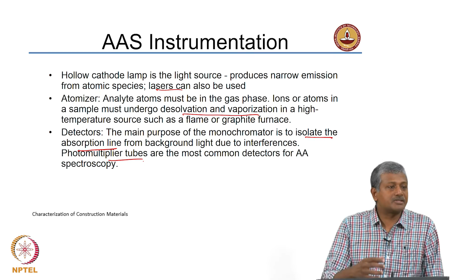So, a detector: basically the main purpose of the monochromator is to isolate the absorption line from the background light due to interference, because we want to only isolate the incoming radiation. We know exactly the wavelength of that and we want to only isolate that, so that we can attribute it to absorption by the specific species. And photomultipliers are used to amplify the intensity of the outgoing radiation sufficiently, so that we can show that as a result.